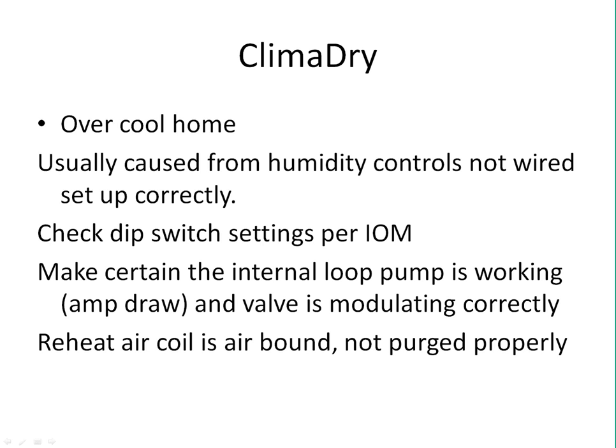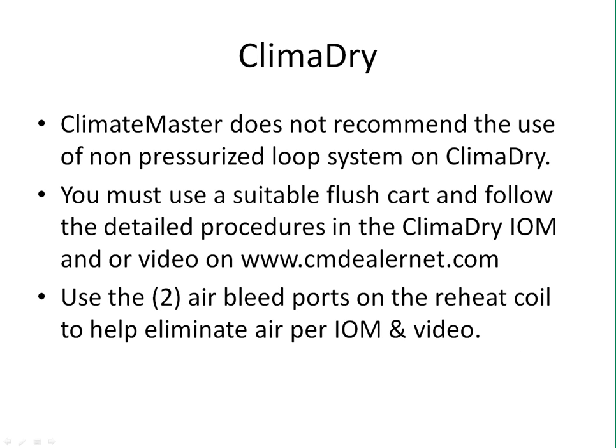The other area that we oftentimes see if it's an overcooling situation is that the reheat coil is airbound. Basically, guys, it's a water-to-air coil. It's right behind the DX coil near the fan. It is frequently not purged properly, and that is not something that the loop pumps or that onboard ClimaDry pump will have any prayer of removing the air from. It must be used with a proper flush cart. You must follow the procedures outlined in the ClimaDry IOM.